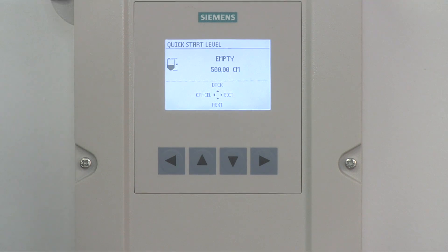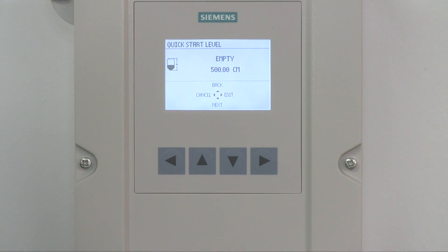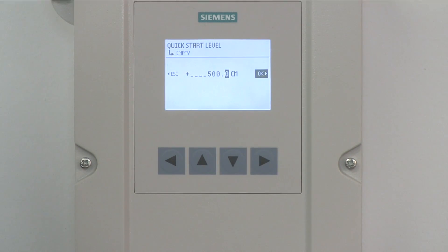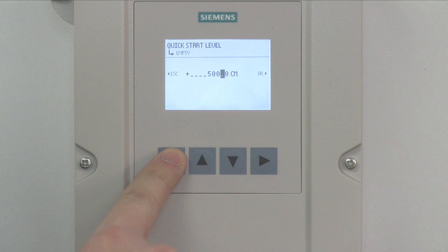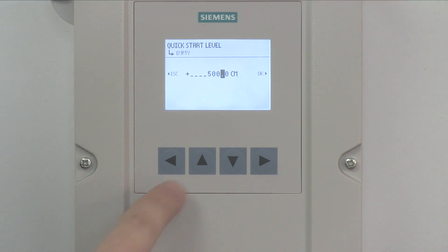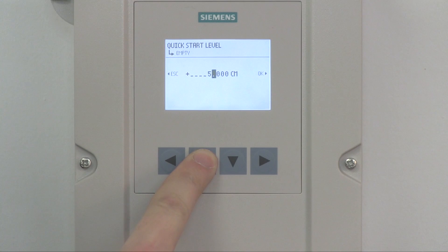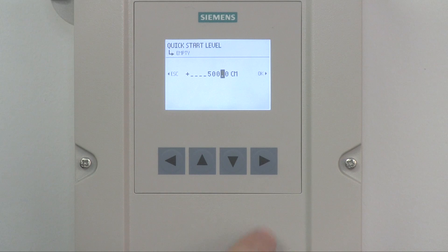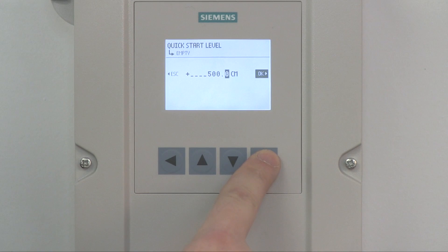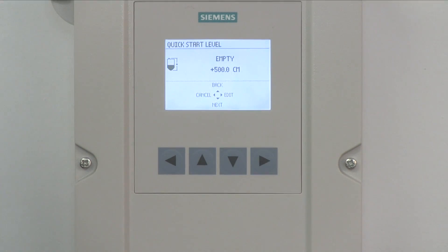The next step in the wizard is to enter the empty distance. The empty distance is the distance from the face of the transducer to the process empty point. Press the right arrow to select Edit to modify the empty distance value. Use the left and right arrows to move the cursor, and up and down arrows to modify the empty distance value. To move the decimal point, position the cursor over the decimal point and use the up arrow to move it to the left and the down arrow to move it to the right. Once you have entered your empty distance, press the right arrow to highlight OK, then press the right again to accept the empty distance.